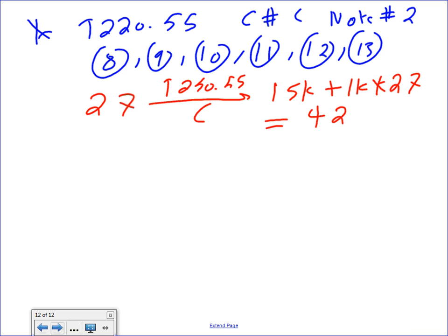42 kW. Everybody knows where we came up with that? For 27 of them, the demand is 42. Had they been all 12 or less, I'm done. But there's one problem. Some of them are 12, some are less, some are more. So I have to apply note number 2. Keep this 42 in your mind first. Okay, let's go do the second calculation.